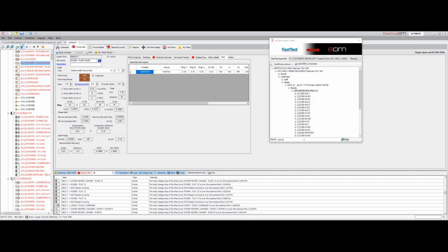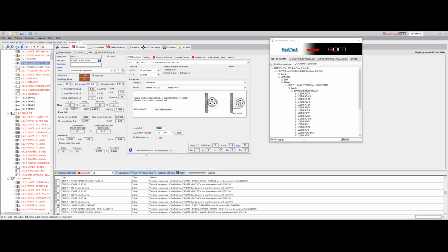We've taken values like R1 and R2 and used that information to estimate the length of the cable run, which gives us an idea of what the volt drop levels should be for that system. So we can see where we've exceeded those volt drop levels.